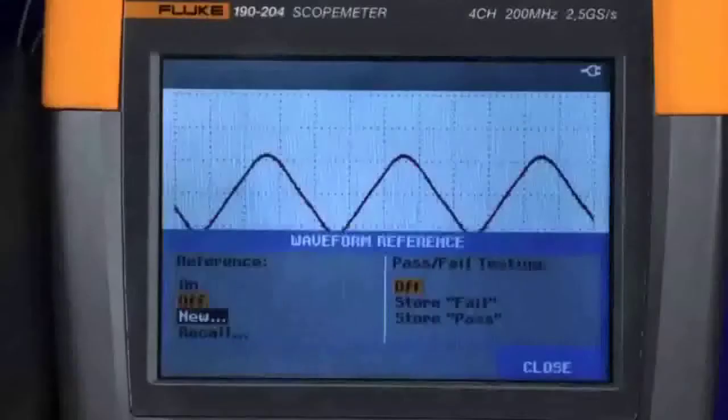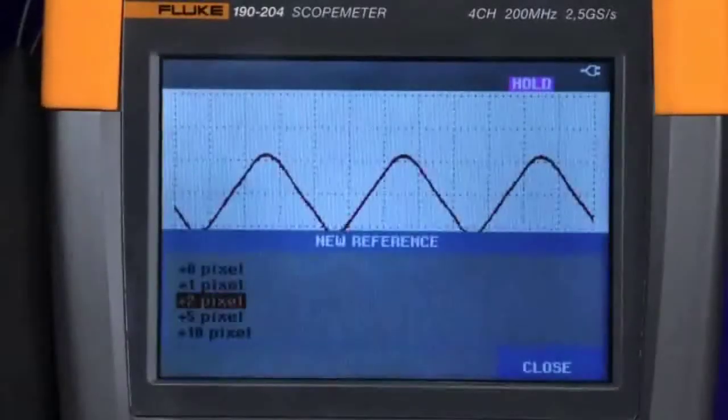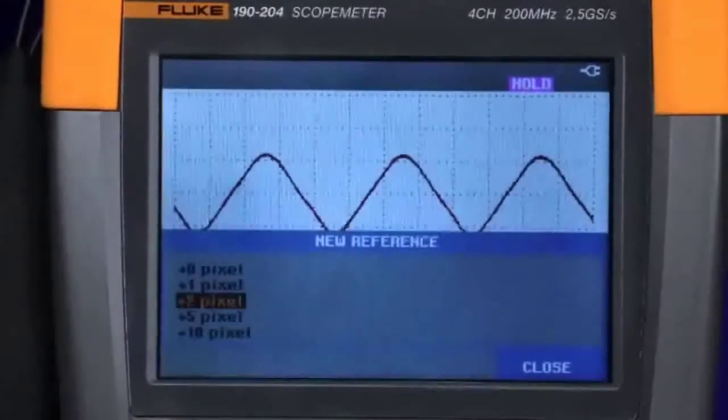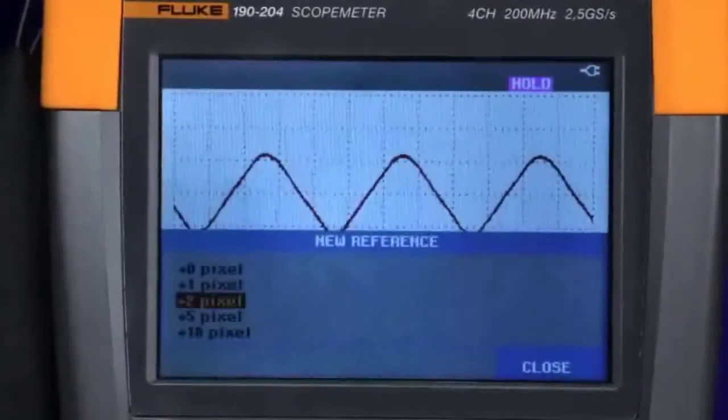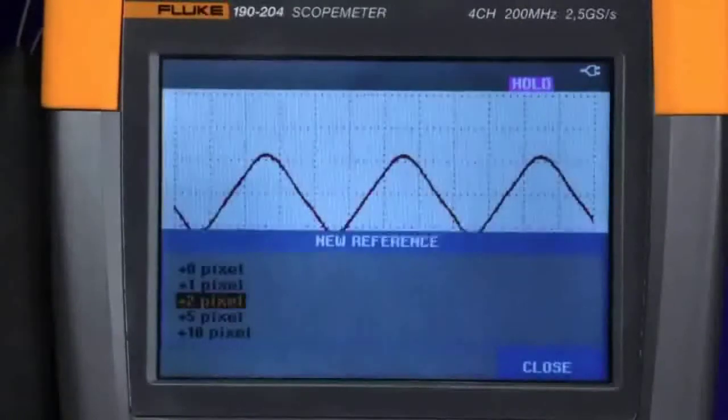Here is where you define the window of tolerance by the number of pixels. In this instance, we'll choose a relatively tight window by selecting plus two pixels around the known good waveform, then pressing enter.